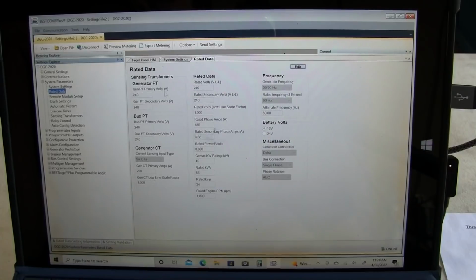Rated data, also another important one. So generator potential transformers, PTs, bus potential transformers, we're not using any of those. So our primary and our secondary voltage is just the same. Generator CT for current sensing. We got 5 amp CTs. The primary amperage is 200. Rated voltage line to line, all that good stuff. And then our battery voltage, 12 volt or 24 volt. This is all grayed out. You have to hit this little button to edit it.